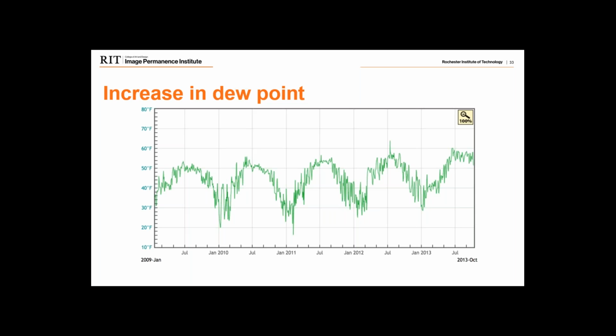So even though we were initially designed for a 45-degree dew point, you can see that as far back as our data goes, we were really getting about a 50-degree dew point. We would expect some loss, so maybe it was never operating fully as intended, but it was better. And if we fast forward a few years, we can see that instead now we're operating at more of a 55-degree dew point.